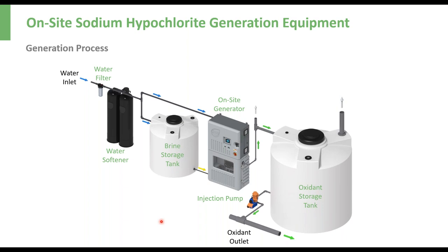Now, the other thing we like to recommend is, when you're dealing with your salt, again, what did I say on the overall generation process is hardness? Well, by nature, salt has calcium in it that helps bind it together. So what we recommend is a food grade salt that has minimum amounts of calcium or calcium carbonate in it, just to minimize your maintenance. So we made the brine solution.